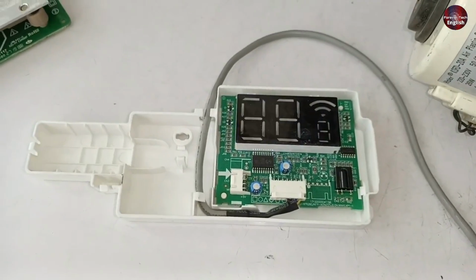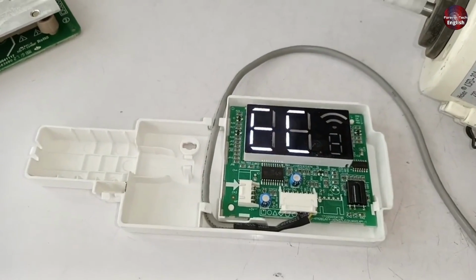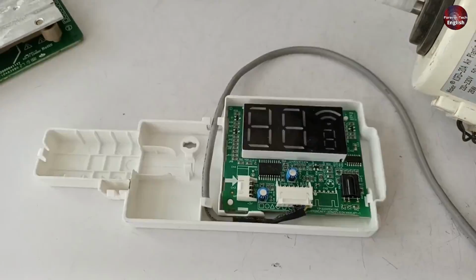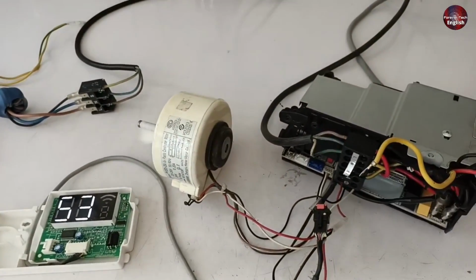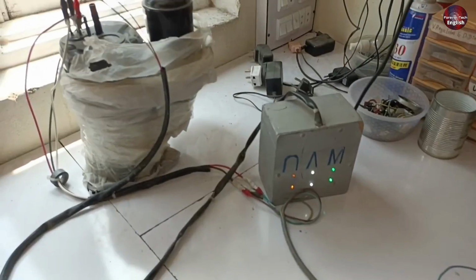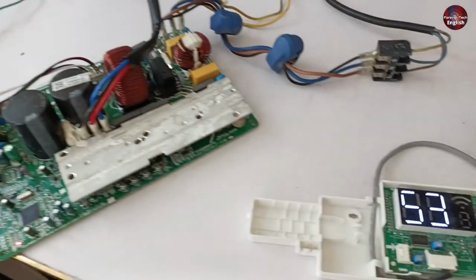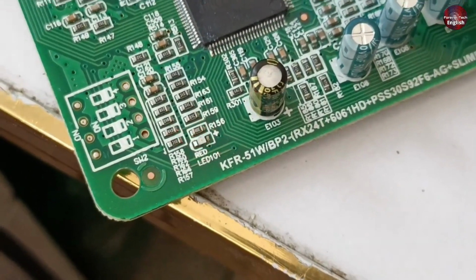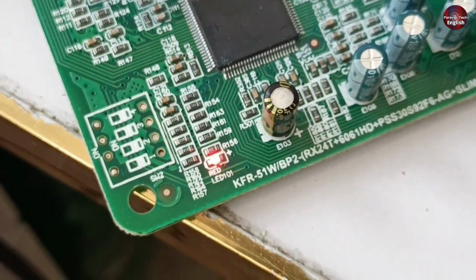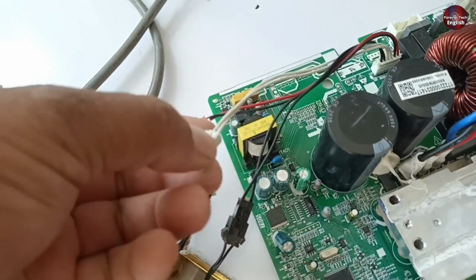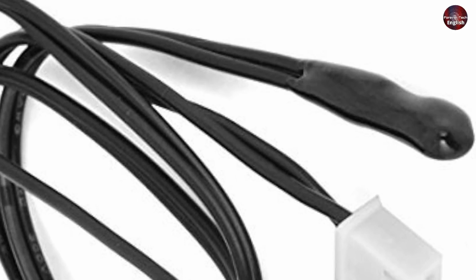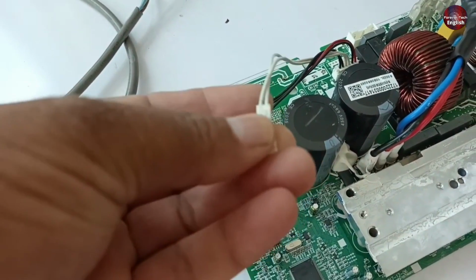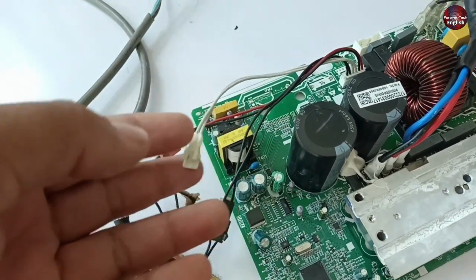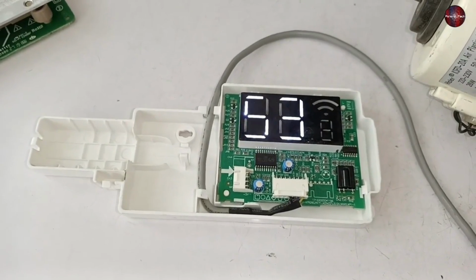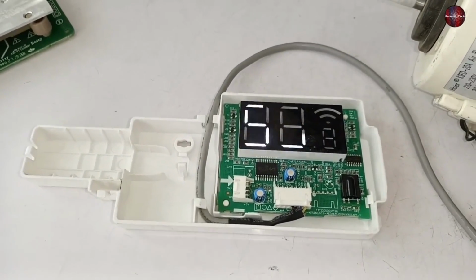The next error that is shown on the display is EC53. Let me tell you about this error as well. During this error, the indoor circuit is working. The compressor has also started to work. It has no issue, but the error is still displayed. The LED light on the outdoor circuit board is blinking rapidly, which means that the circuit board has a problem. The outdoor circuit board sensor, with a white connector, is used to check the ambient temperature. If this sensor is missing from the circuit board or is short-circuited, then this EC53 error will be shown on the display of your mini split air conditioner.